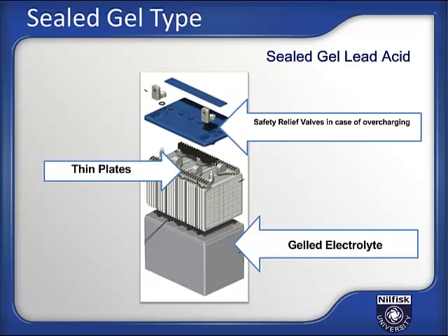Since the battery is designed to be recombinant and eliminate the emission of gases on usage or overcharge, things like room ventilation requirements are reduced and no acid fume is emitted during normal operation. There's also no need nor possibility to check the level of electrolyte or to top up water due to loss of electrolyte. This also reduces your inspection and maintenance.